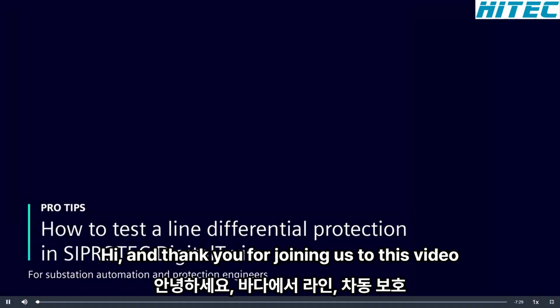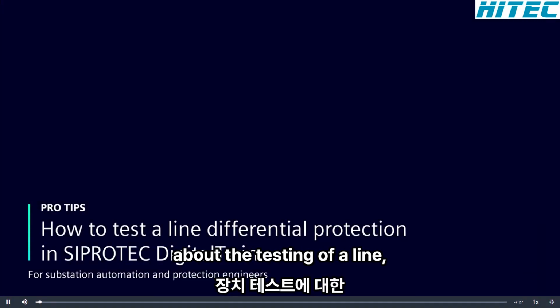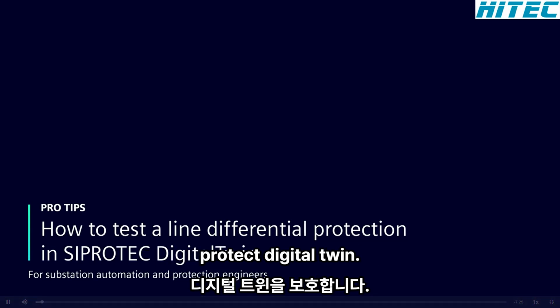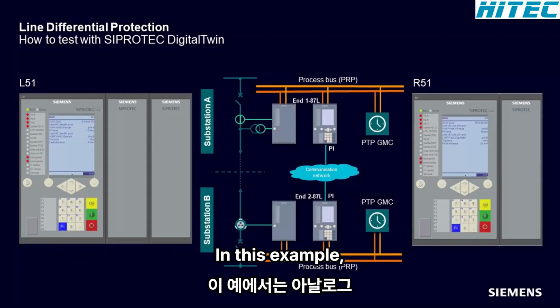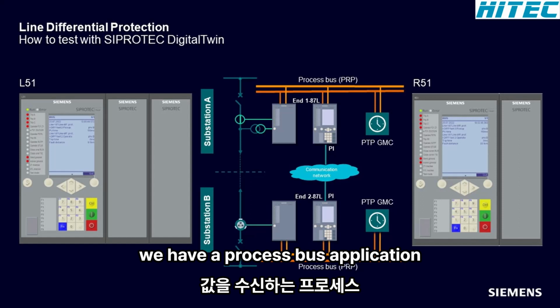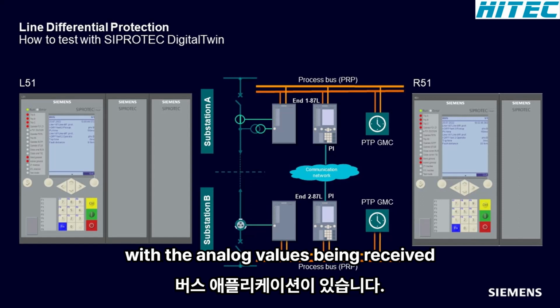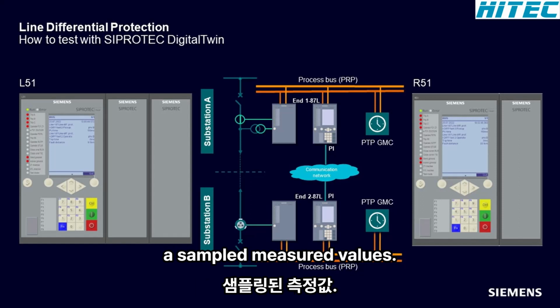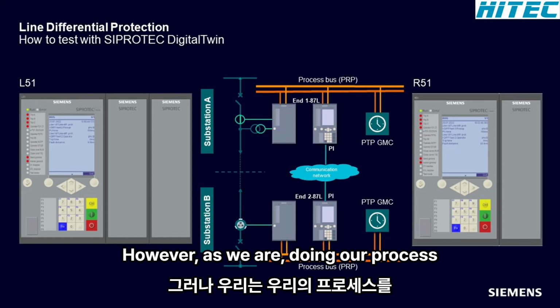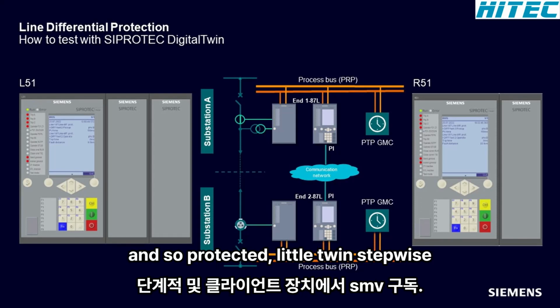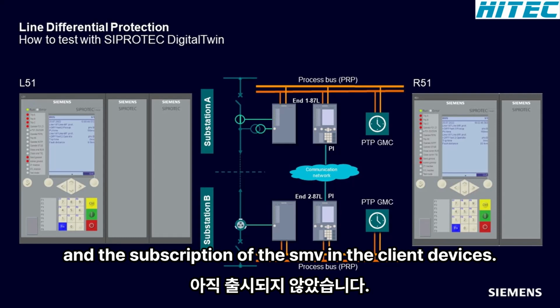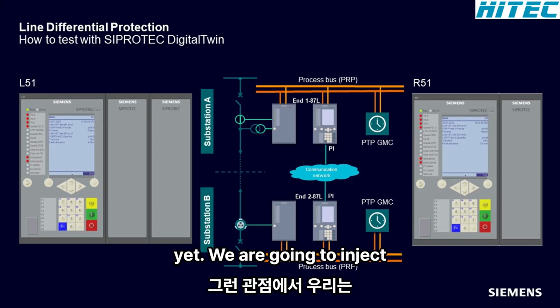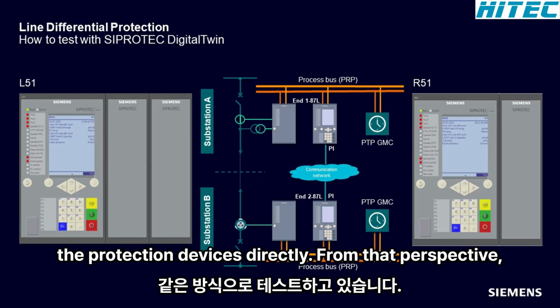Hi, and thank you for joining us to this video about the testing of a line differential protection in the SIPROTEC DigitalTwin. In this example, we have a process bus application with the analog values being received as sampled measured values. However, as we are doing our process bus implementation in SIPROTEC DigitalTwin stepwise, and the subscription of the SMV in the client devices has not been released yet, we are going to inject the protection devices directly.